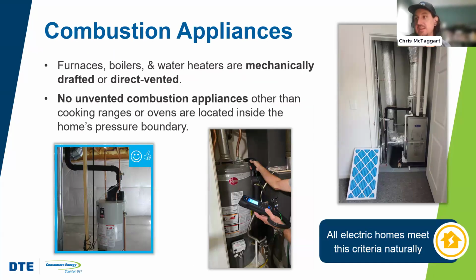Last but not least, in Energy Star homes, you have to make sure that any combustion equipment, furnaces, boilers, or water heaters, are either mechanically drafted or direct vented. What does that mean? Well, it means that either we have sealed combustion equipment like this furnace over here on the right-hand side. It brings in its combustion air from outdoors and it shoots the exhaust gases all the way to outdoors.